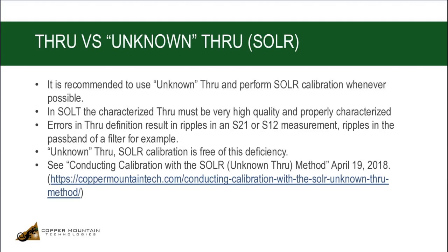So, characterized through versus unknown through. Earlier, when I did the calibration, I had a choice between the characterized through, which has an actual delay associated with this through, or I could have chosen the unknown through. And when I did the calibration earlier, which you didn't see, I chose unknown through.